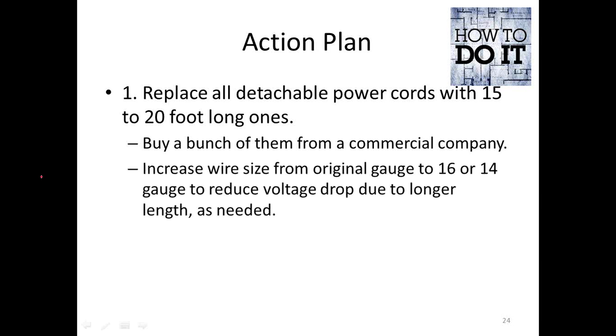Because of the extra length, you may want to increase the wire gauge to either 16 or 14 gauge to make sure that you don't have any amperage capacity issues.